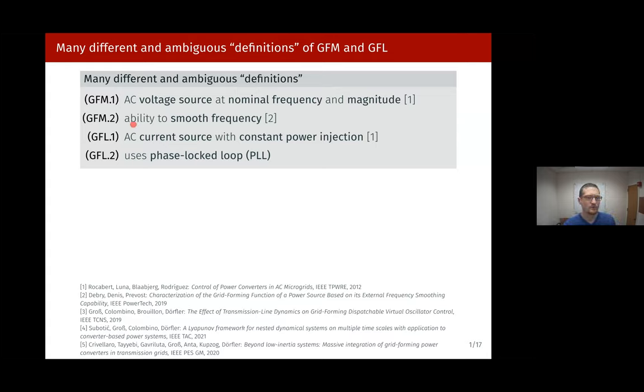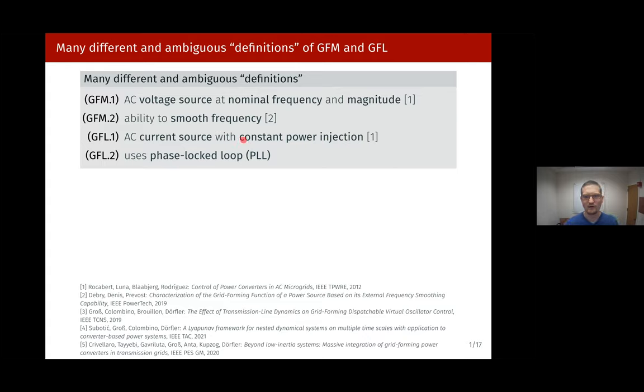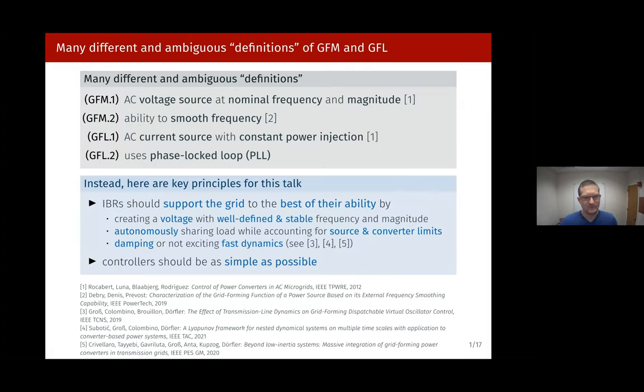Other definitions have emerged that focus on the ability to smooth frequency. For grid following, definitions are equally vague — something you will often see is defining a grid following converter as an AC current source with constant power injection, but even standard grid following control with a phase-locked loop cannot always induce that behavior. Some definitions center around whether a PLL is present, but that's also problematic because there are grid forming controls that use PLLs in auxiliary roles that most would still agree are grid forming.